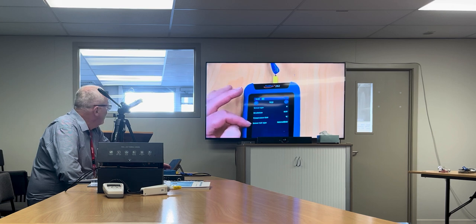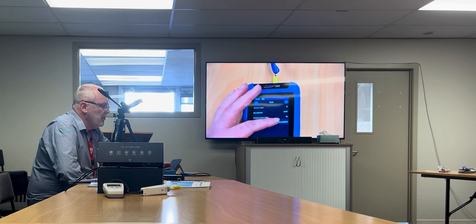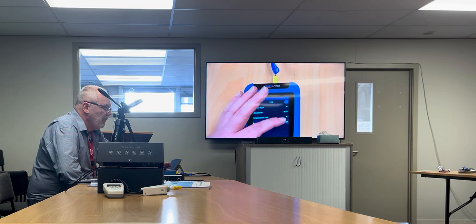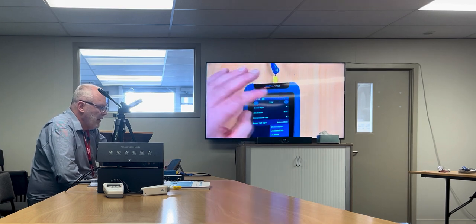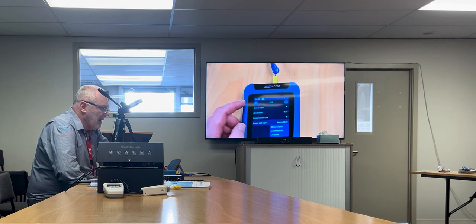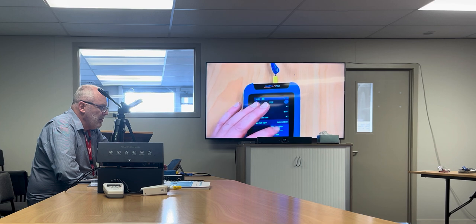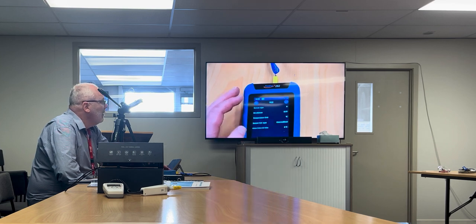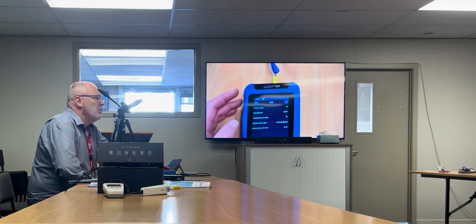And here's your cold junction compensation. At the moment it's set to internal. There's two things you can do. Now this is where it's lost in translation just slightly. External means you're putting in a figure - you've measured the temperature where you're working and it's exactly, you know, 19.3.